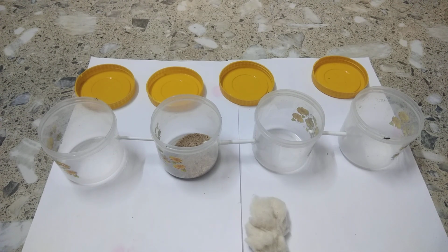And the next step is filtration. Once the flocs have settled to the bottom of the water, the clear water on top is filtered to separate additional solids from the water. During filtration, the clear water passes through filters that have different pore sizes and are of different materials such as sand, gravel, and charcoal. These filters remove dissolved particles and germs such as dust, chemicals, parasites, bacteria, and viruses. Activated carbon filters also remove any bad odors.